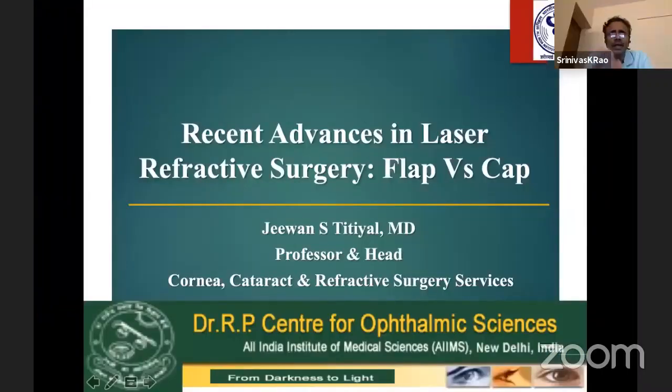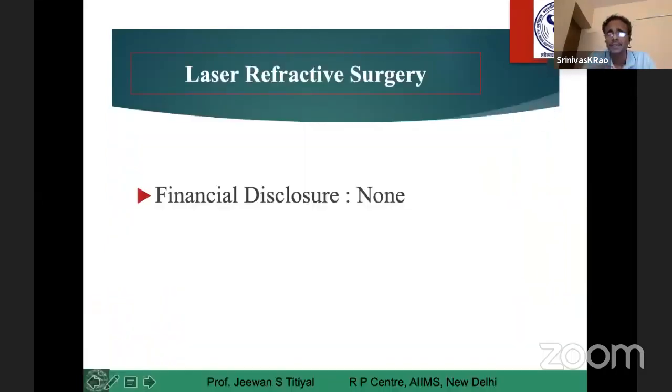Of Scheimpflug technology, the main advantage is that you can look at the posterior corneal surface without having to look through the anterior corneal surface, like the slit scanning which the Orbscan does. If you have a keratoconus with a distorted surface through which you're looking at the posterior surface, or a post-LASIK eye where you have flattened the anterior surface, the posterior surface imaging is not very accurate. Whereas with the Scheimpflug, because you're looking at it as a side profile, the data is very accurate. So that's the most important advantage.